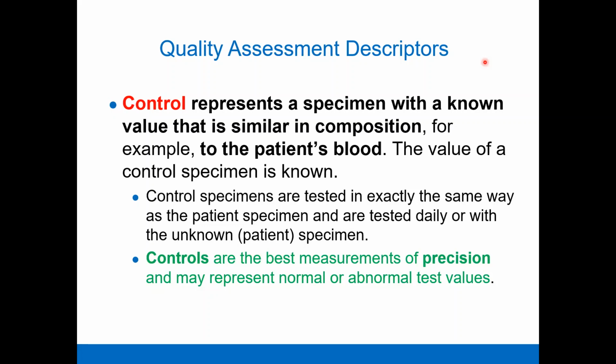Okay, if you know the level of the samples, which is control, then you are going to measure the same test repeatedly 10 times, 20 times, and see how close to one another the results are. And which gives you the precision of the test.